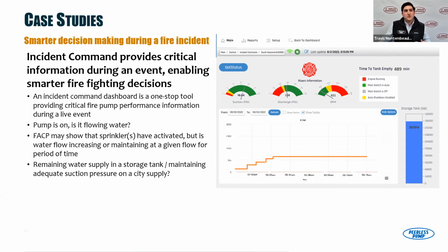What we're trying to do for the fire site leaders, for the incident commanders, for the emergency responders, is give them the data that they haven't had before, which is: is the pump running as it should? Does it have adequate supply? What is it flowing at? Does it still have more to give based on the rating of that fire pump? And what is the current performance? And they can take all that information and make a decision. And for me, hopefully that decision is they leave the fire pump on, because that's step one. Let it do its job.